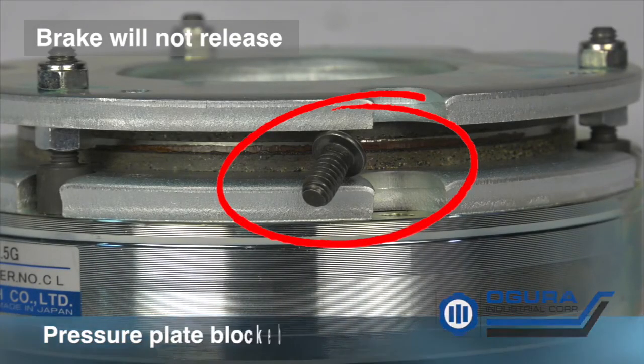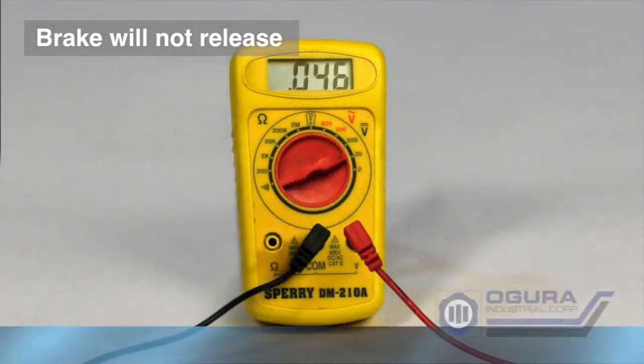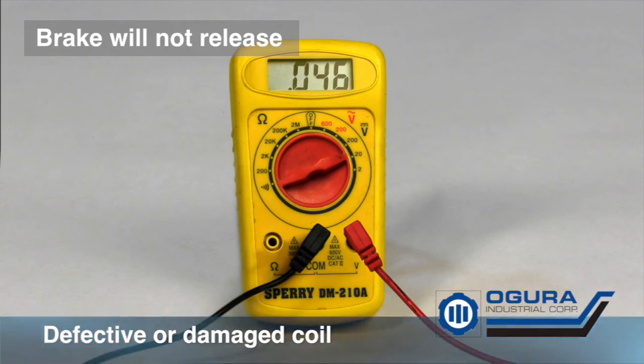Pressure plate blocked. Check to make sure there is nothing wedged between the pressure plate and the coil housing. Defective or damaged coil. Check the ohm rating on the coil.